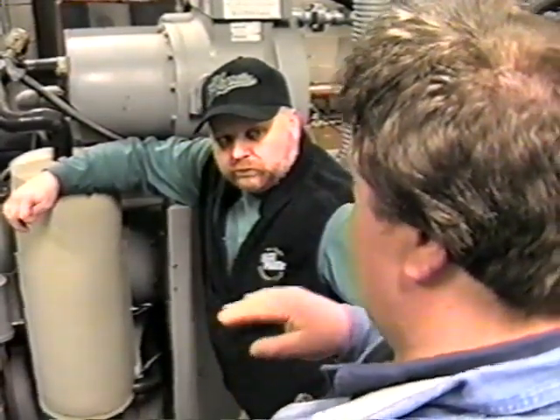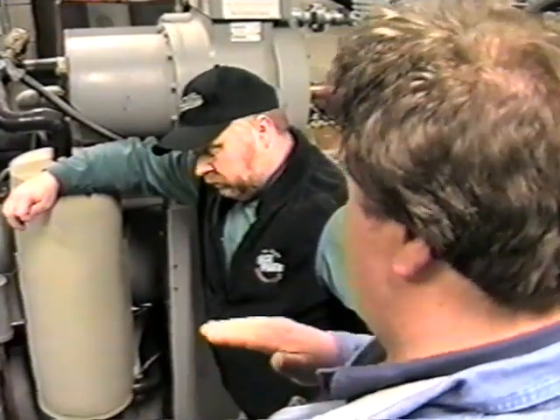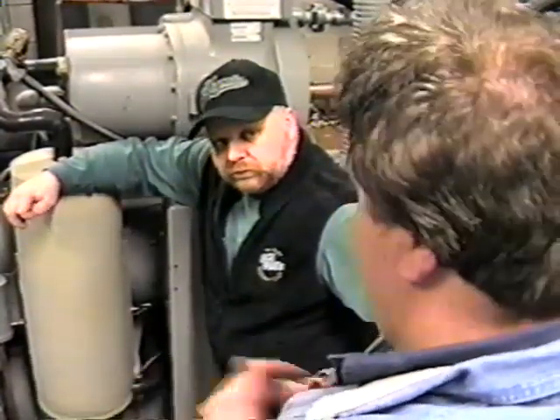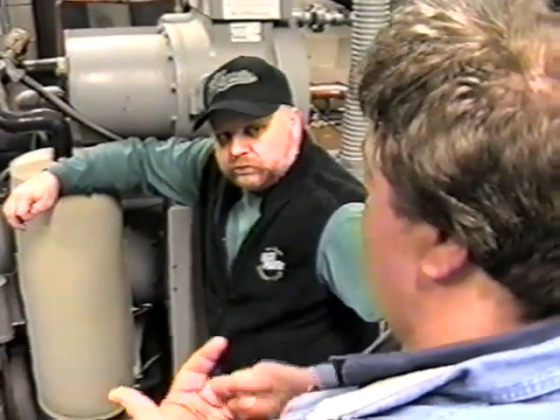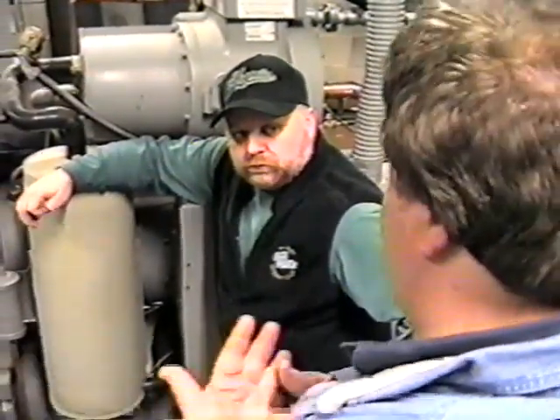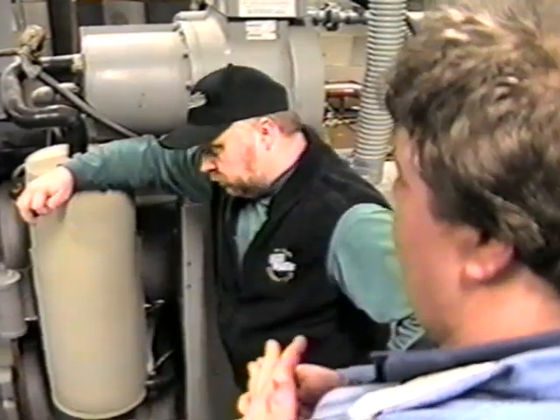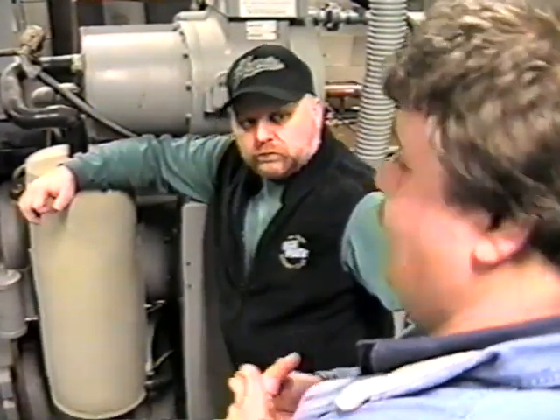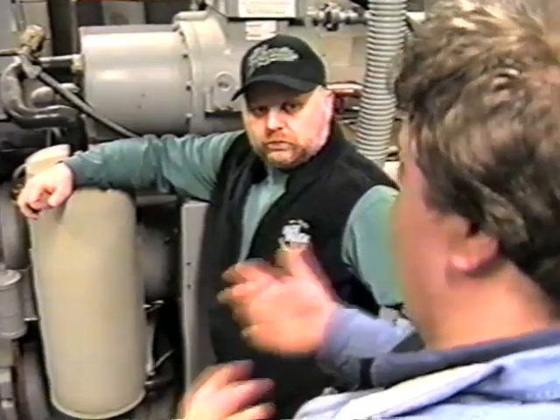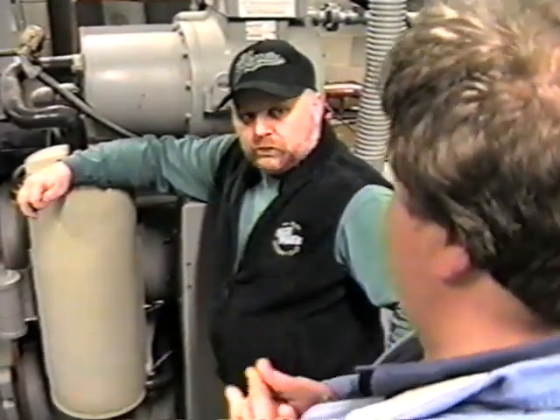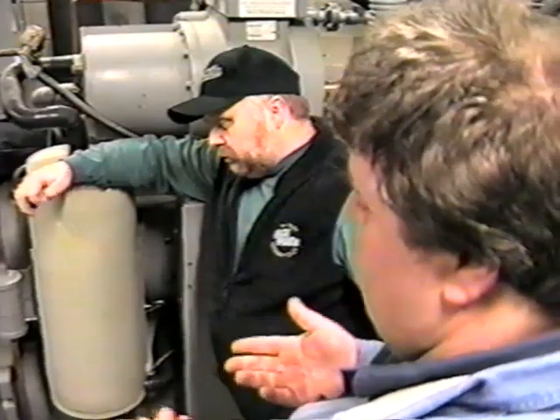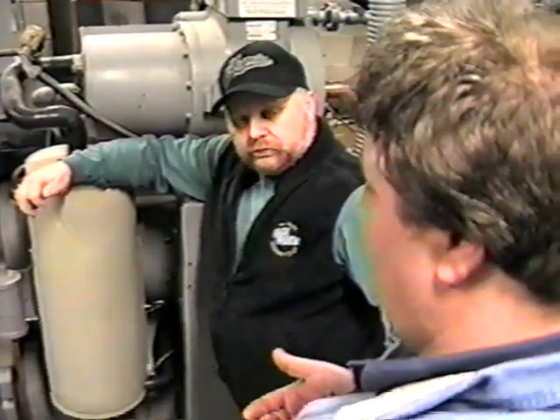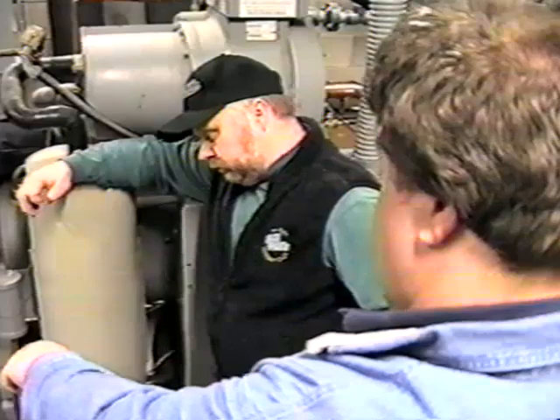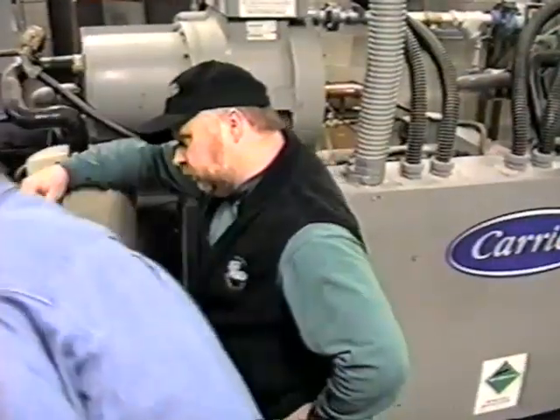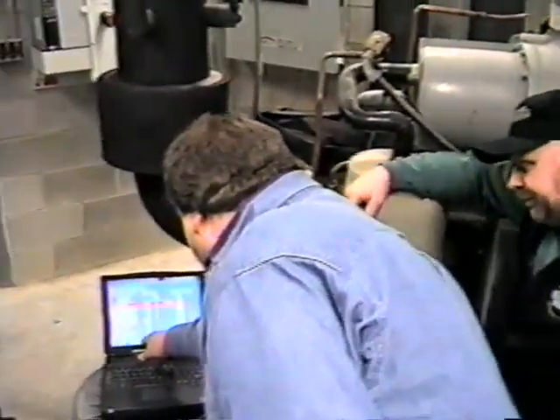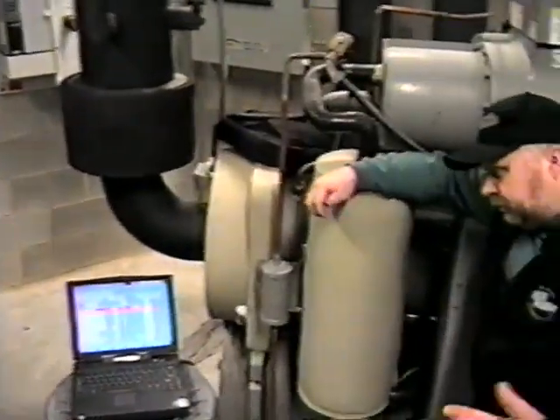As long as your sump temperature is above 70 degrees, your underfloor heat is enabled, and it will try to control at 55 degrees. You're going to find that it doesn't run an awful lot because you get excellent heat transfer here, and it warms up pretty quick, and then it holds. If the sump water temperature dropped below that, what you're seeing right now is on this underfloor heat pump start function, right? That it is stopped and that I've got a control on there.